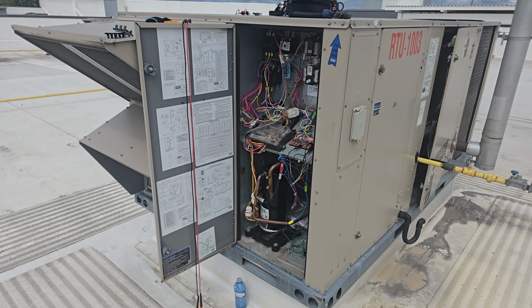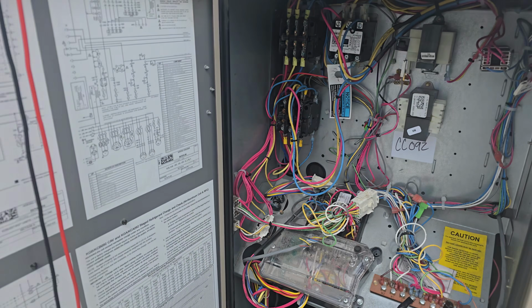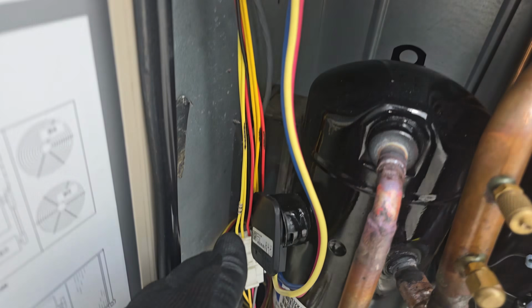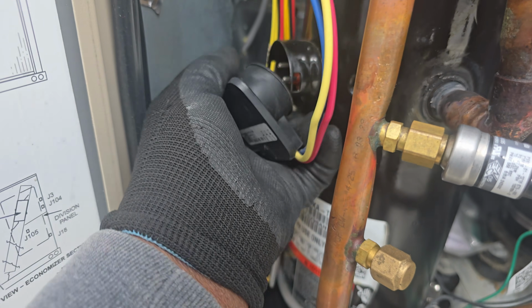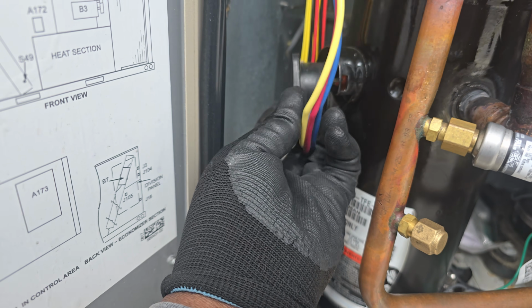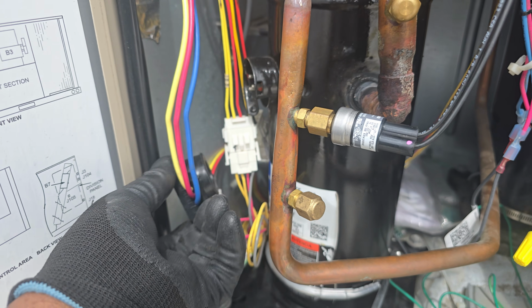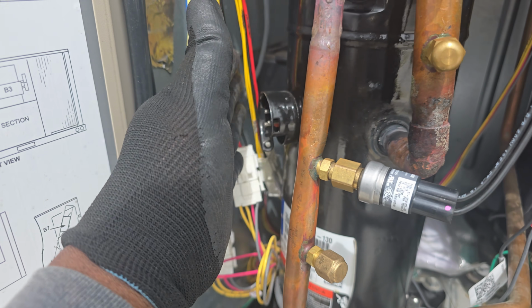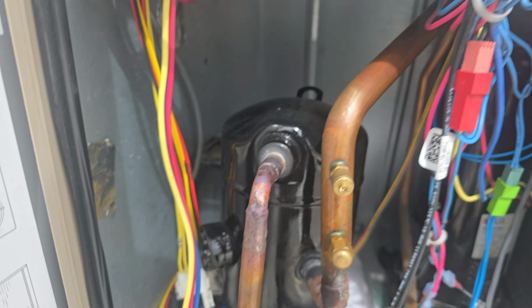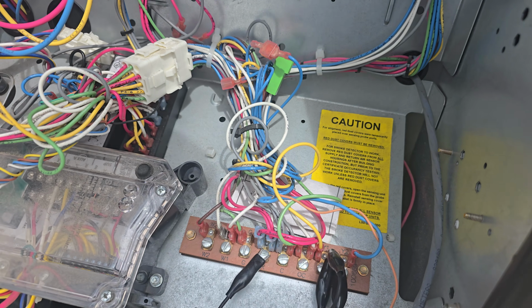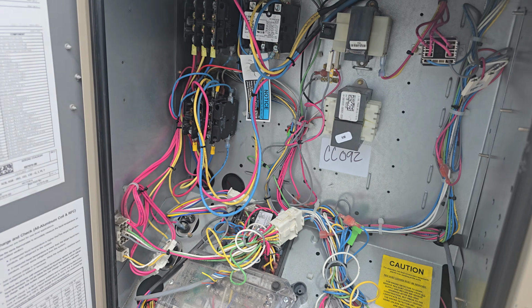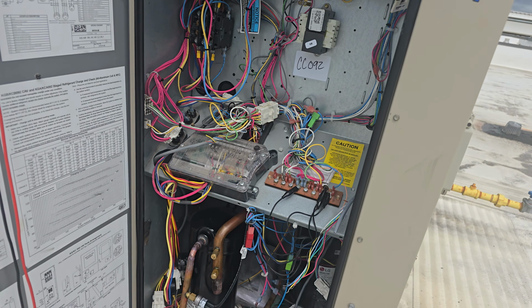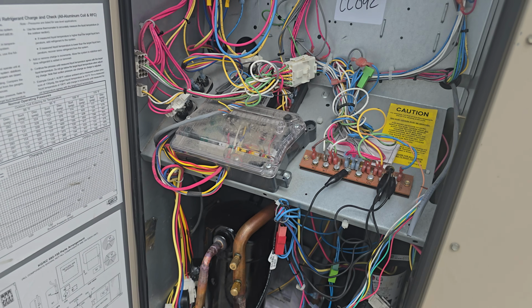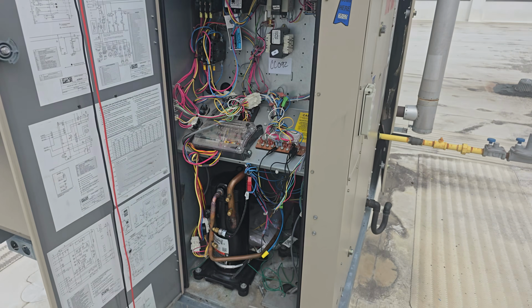Okay, so my next step now is to disconnect this connector here to the compressor, so I'm going to take that off. That means I have isolated my compressor, and remember my jumper is still on it here, and I'm going to just turn on the unit. I want to see if that trips off again, then we know we have eliminated the compressor. So I will let you know.